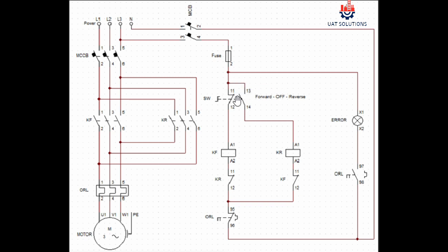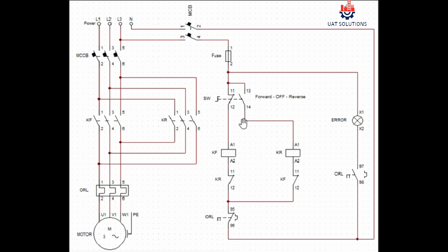Point 12 of selector switch is used for forward function and it is connected at the KF contactor coil terminal A1. And point 14 of selector switch is used for reverse function and it is connected at the KR contactor coil terminal A1.